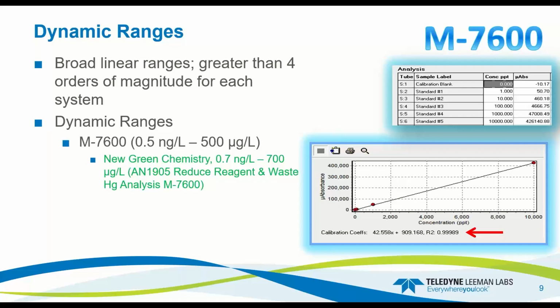So with that said, on the system, when we take the 4-channel 12-roller pump, the mass flow controller, the gas liquid separator, and everything else that delivers precise solutions with a stable gas flow to the system, you get very, very precise results. So most of the time, we are going to say we're going to get at least 3 nines in almost any range, including the green chemistry range of 0.7 to 700 ppb. Here's an example where we were calibrated from a 1 ppt to a 10,000 ppt or a 10 ppb, and we achieved 3 9s and an 8 9 on that calibration.